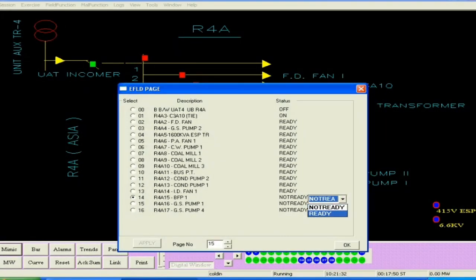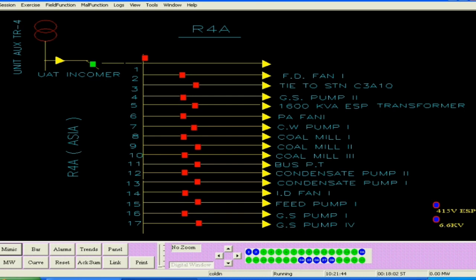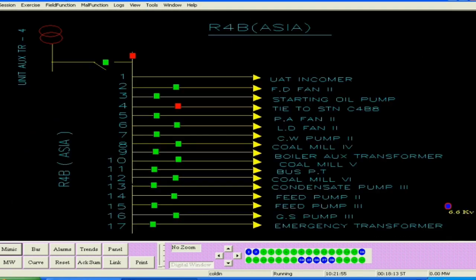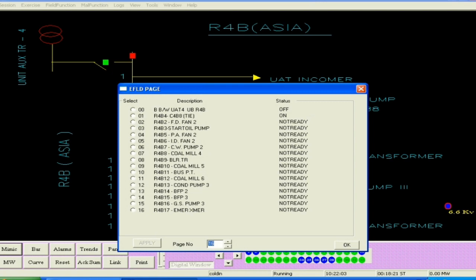Then on the R4A board, there are some breakers on field page number 15 also, from index number 2 to index number 16. You can see the R4A board has been charged. Similarly, we can charge the R4B board. This is the R4B board. On field page number 16 you can make the breakers ready, from index number 2 to index number 16, so that all the breakers will be ready. These are the 6.6 kV unit auxiliaries. Those will have to be made ready so that they can be operated from remote.